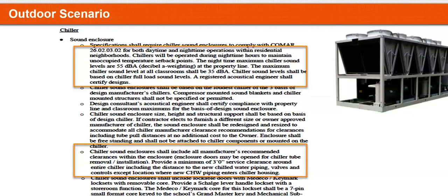Traditionally, the rule is do not obstruct airflow into a chiller or you're going to impact performance. Typically, as long as you keep a barrier wall 3 feet away for a single chiller, that is acceptable by most manufacturers. And now, don't forget, you have to also account for the environment. If you're close to the coast, likely you're going to have to powder coat or you're going to have to use 304 or 316 stainless steel.